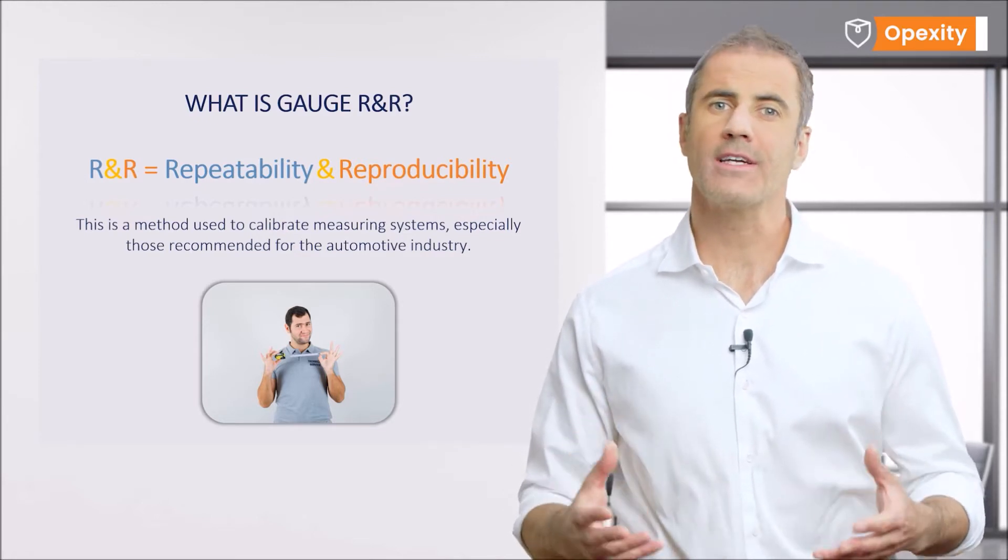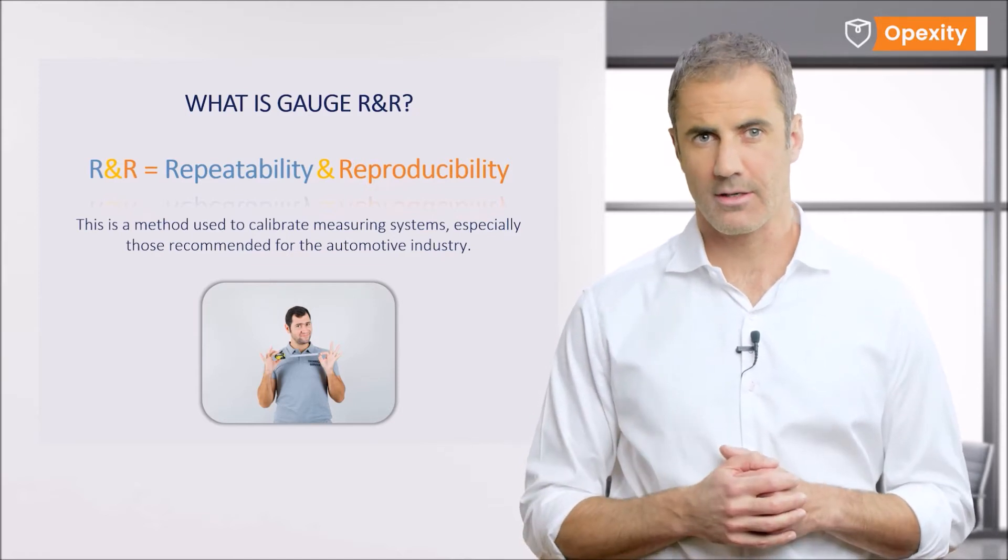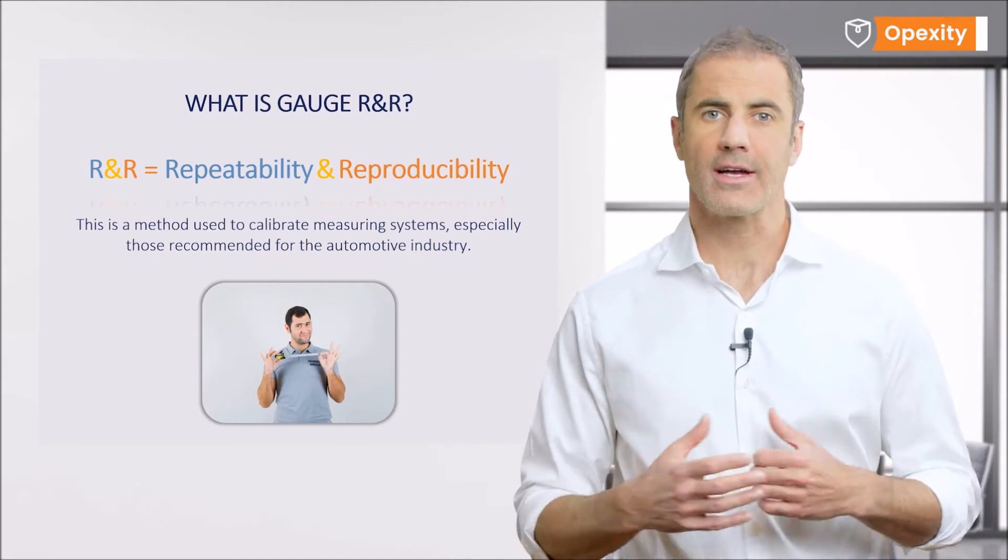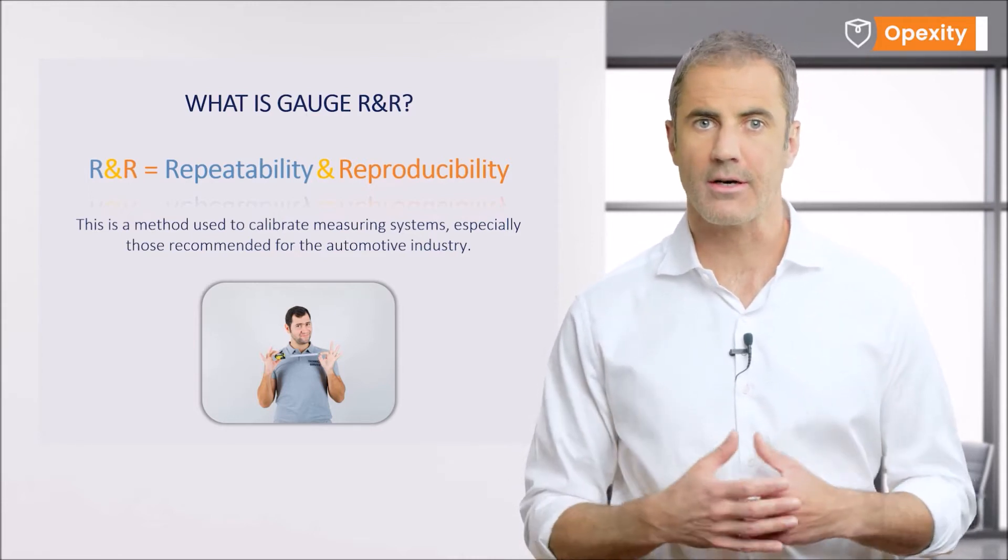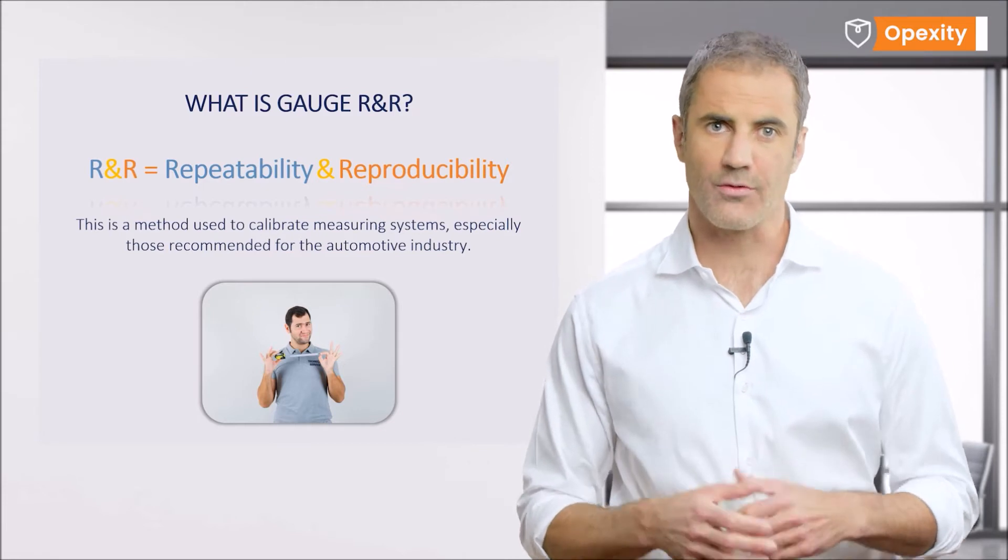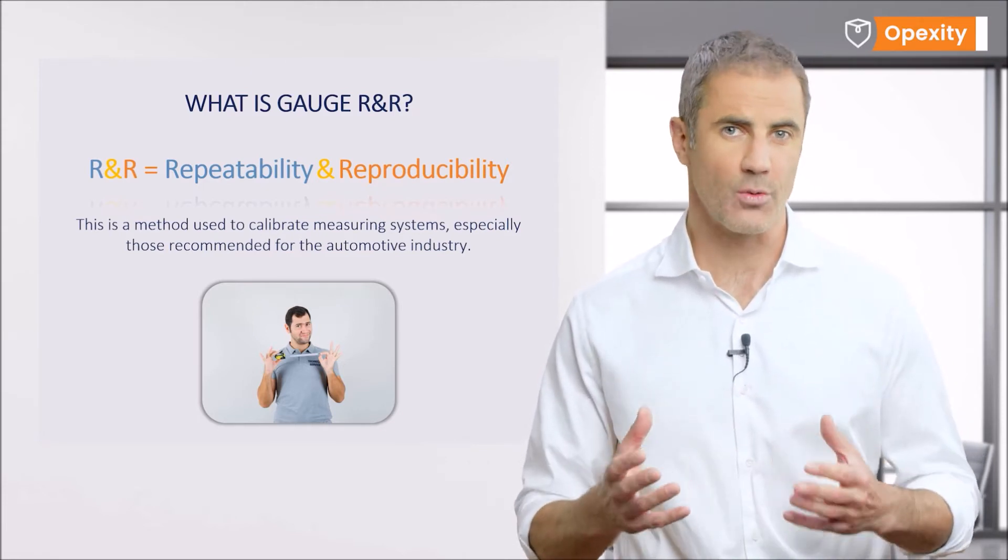This method provides a quantitative means of selecting a measuring instrument and is used to decide whether a given instrument is suitable for evaluating the product or process parameter with regard to its actual variability or the variability defined in the specification requirements.